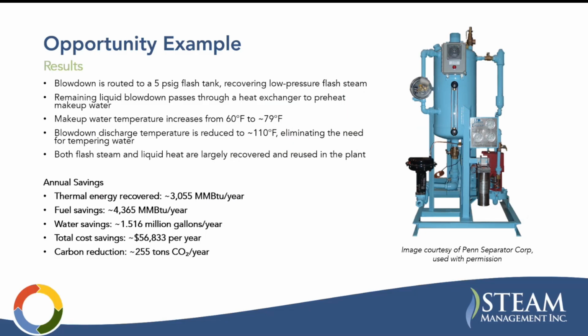The results from this particular example: you're going to take that blowdown and route it to a 5-pound flash tank, recover that low pressure flash steam, like we've been saying. The remaining liquid blowdown passes through a heat exchanger to preheat makeup water. The makeup water temperature is going to increase from 60 degrees to 79 degrees. So that's the impact there.